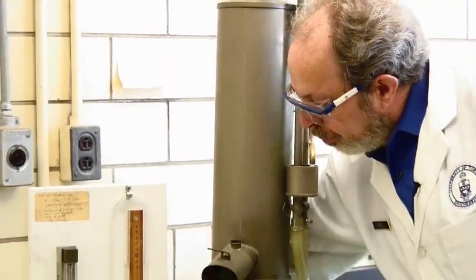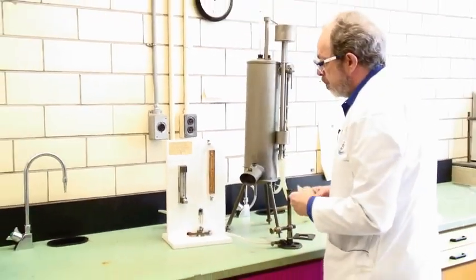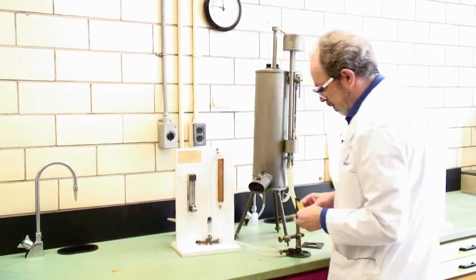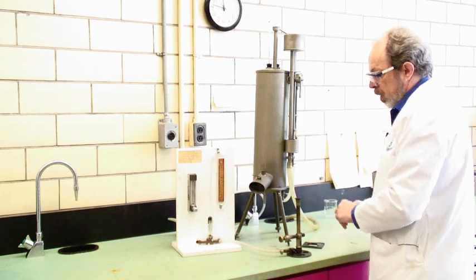Turn the gas on and have a match ready and then open the rotameter and get about 50 percent flow. Strike a match and light.